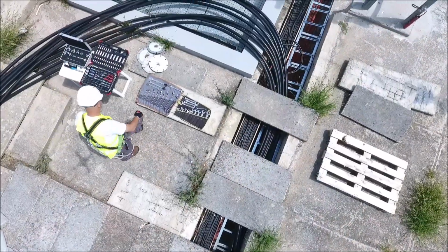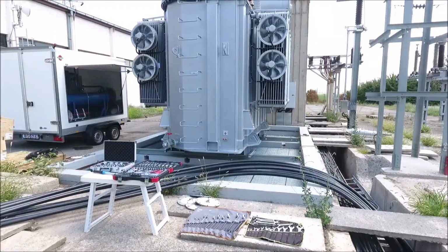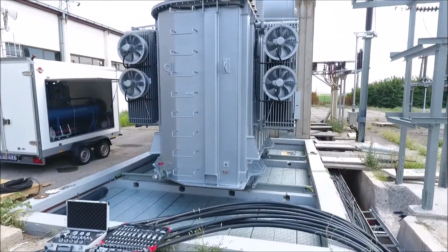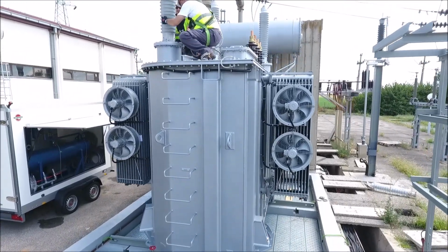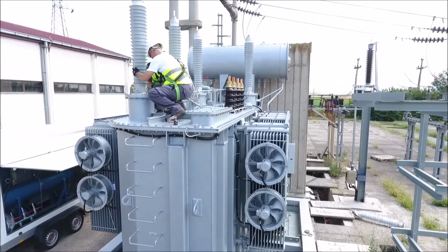In most cases the transformer oil is not filled in the transformer, so after the mounting of the auxiliary equipment, there are some additional fillings of the transformer with transformer oil.